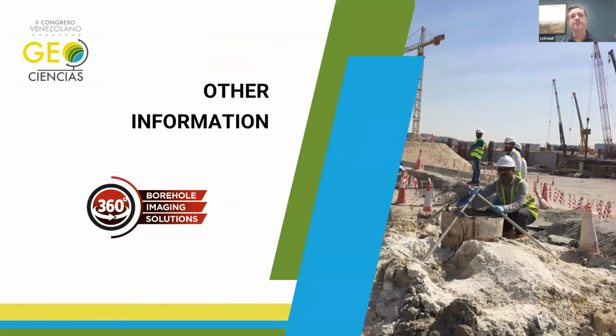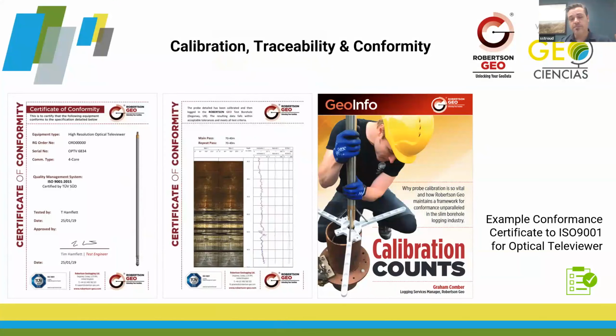Really quickly, other information. Calibration, traceability, and conformity is very important. Clients often want to know when the last time the equipment was calibrated. If you do have a certificate of calibration at Robertson Geo, everything is temperature tested, pressure tested, and borehole tested prior to leaving the facility. And it all comes with a certificate of conformity stating that it has been through these procedures and has been signed off, so you get a date and a signature from the engineer that tested it.